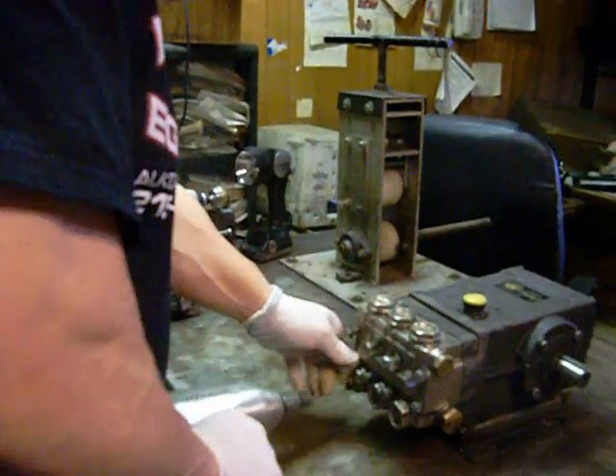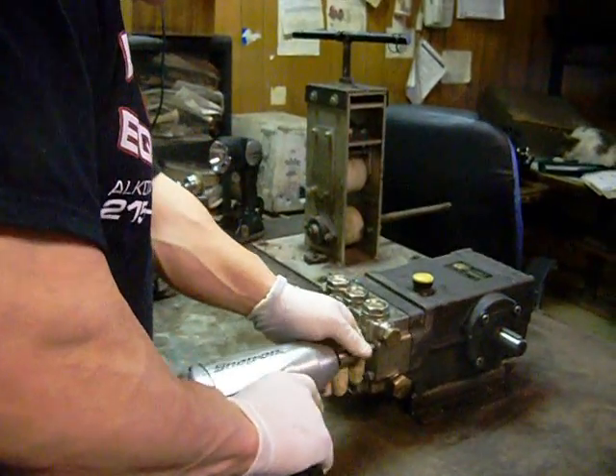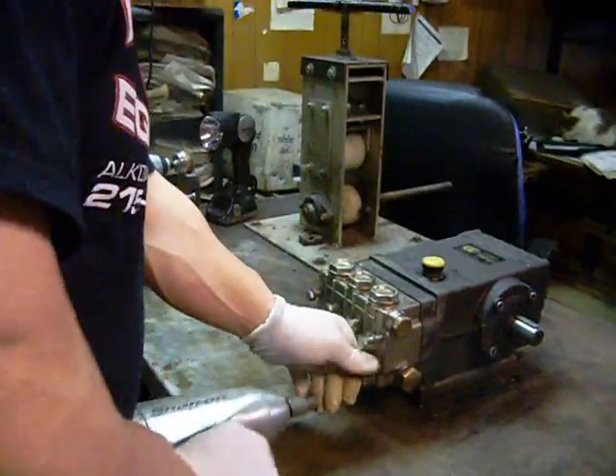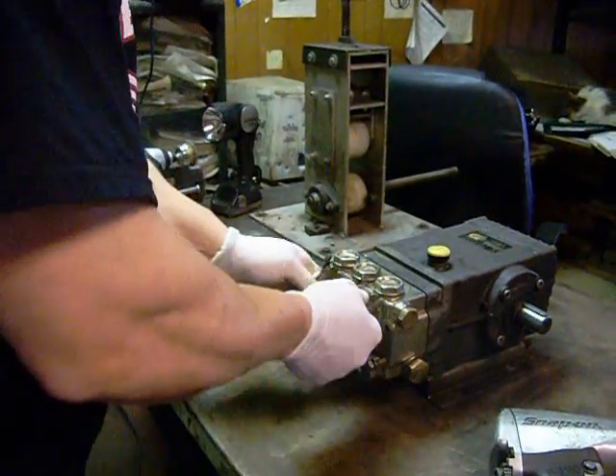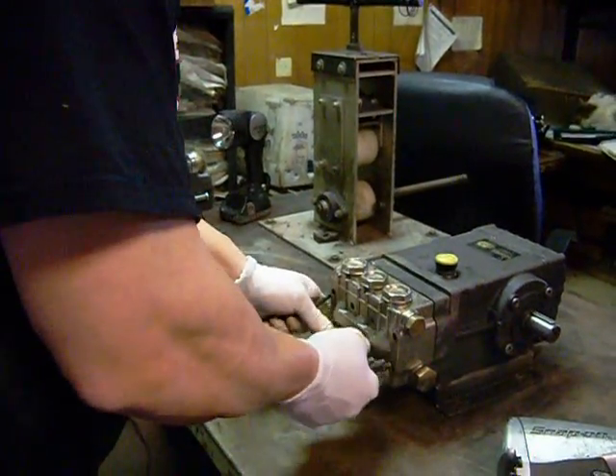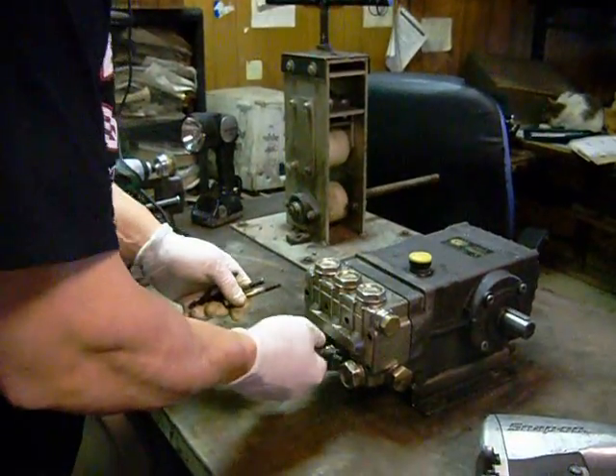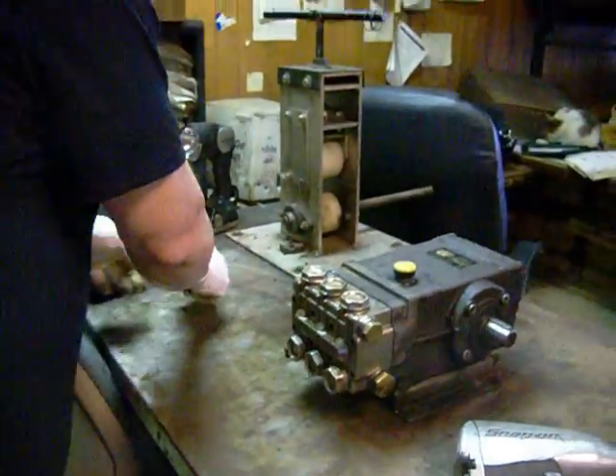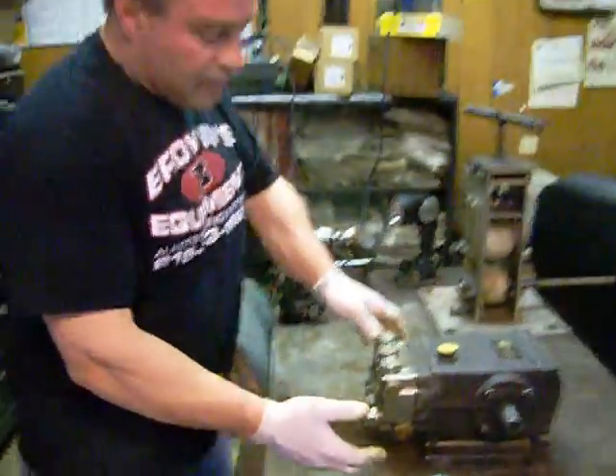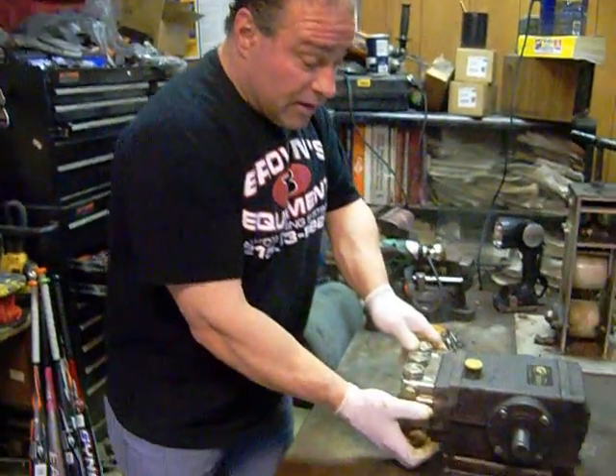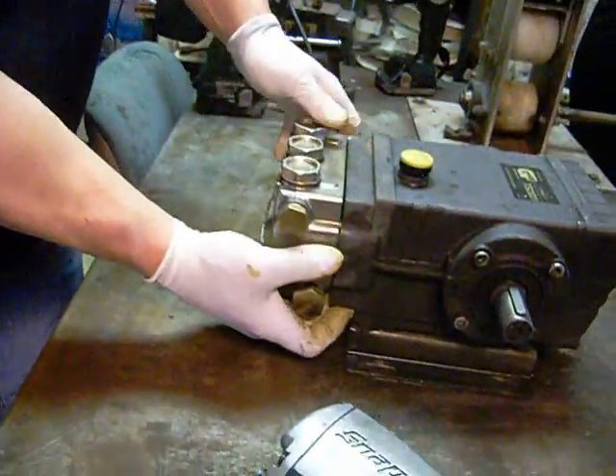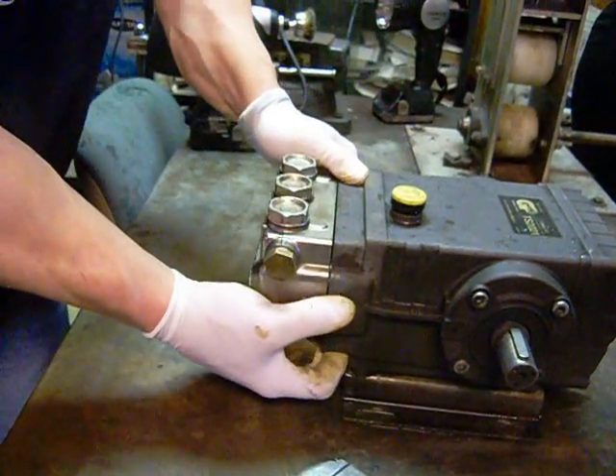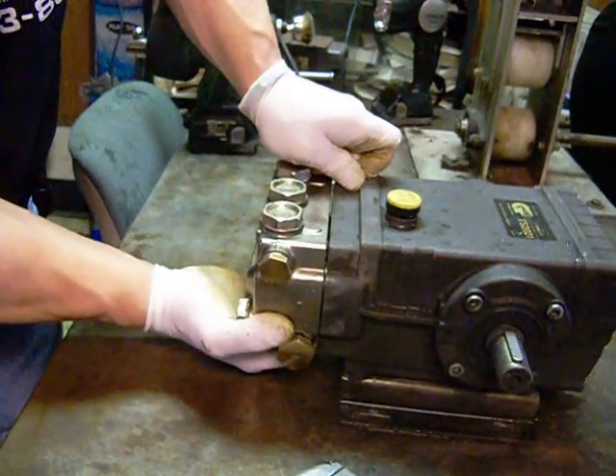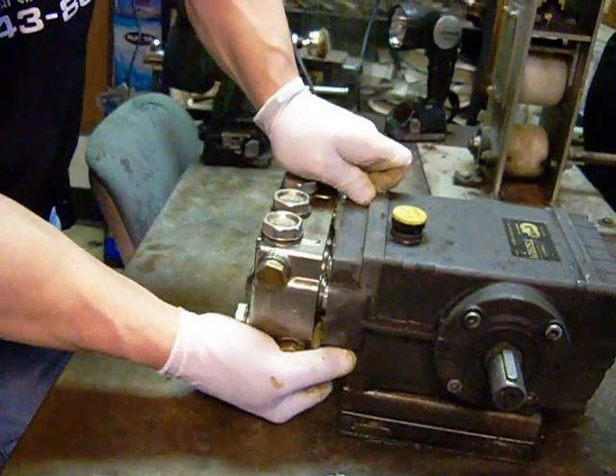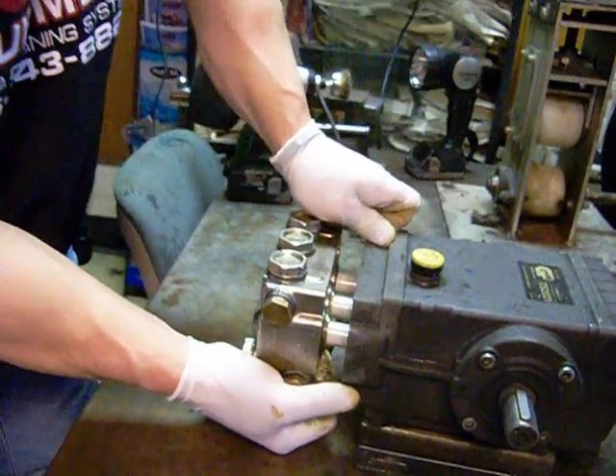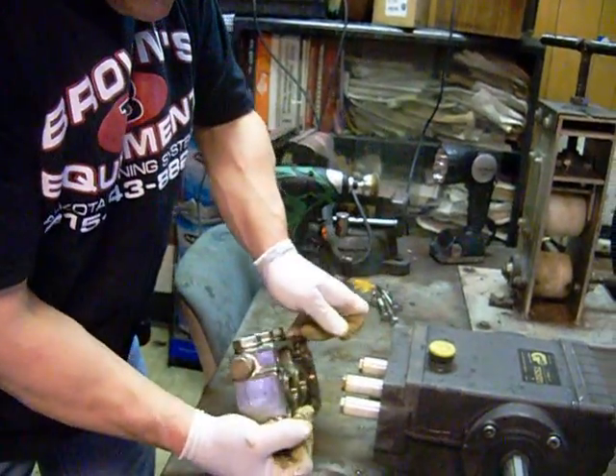Alright, we're going to remove all 8 head bolts. Sometimes when you're pulling the head of the pump off, it may be a little harder to get off, other times it comes right off in your hands. This pump has been in service a little while, so she may come right apart if we're lucky. Basically I'm pulling on the bottom of the pump and the side, and the head will slide right off in our hands.